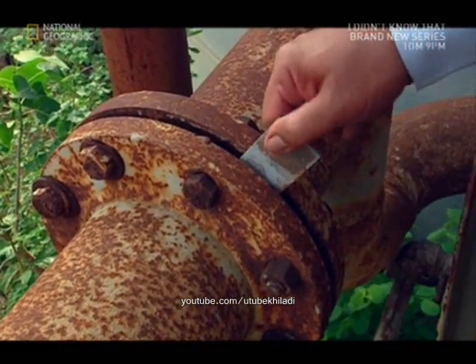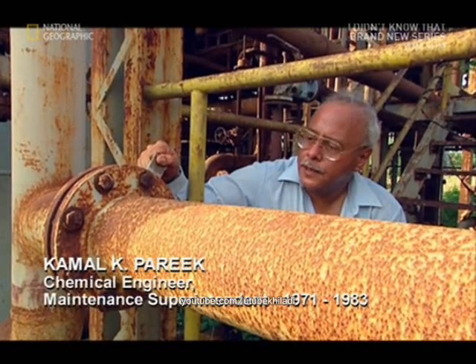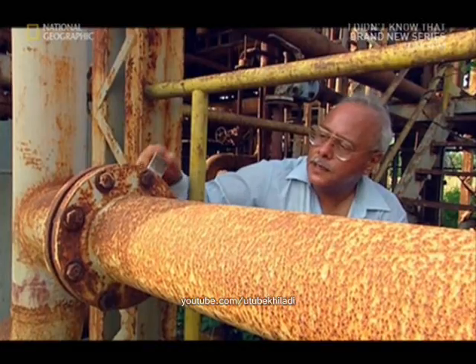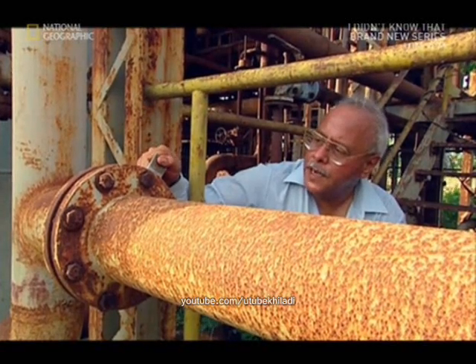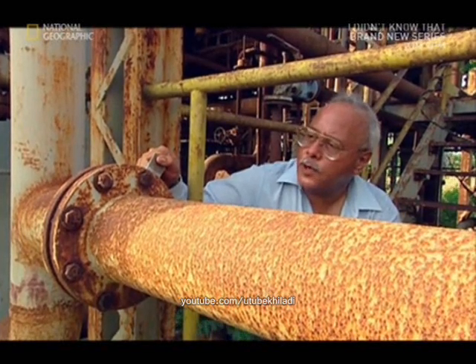A simple piece of metal called a slip blind is inserted and the bolts done up tight, achieving an impenetrable seal. To install a slip blind like this would probably take about two hours, and you would have had to wear a lot of protective clothing, because when you undid the bolts of these flanges, the possibility of chemicals splashing onto you would be there. If one of these small pieces of steel had been inserted into the process pipeline, in all probability this disaster would not have happened.